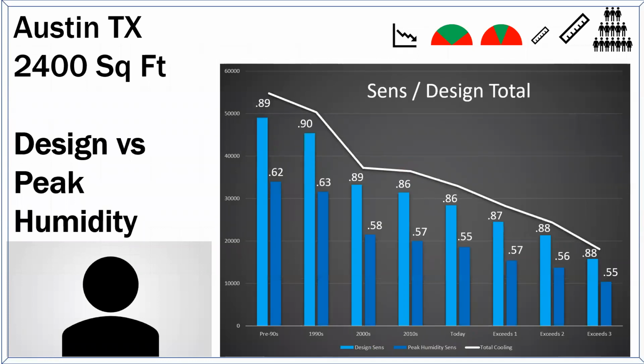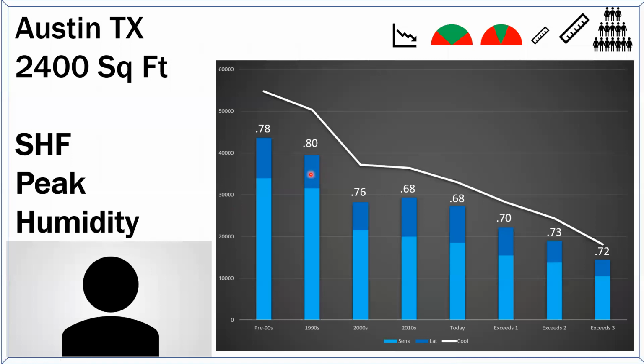Okay, so if we compare these things - if we compare the design peak to the humidity peak, and we look at the sensibles, just the sensibles - this was looking at the total loads. That means a big latent load was counted in this one. So this looked bad, but here's the thing.